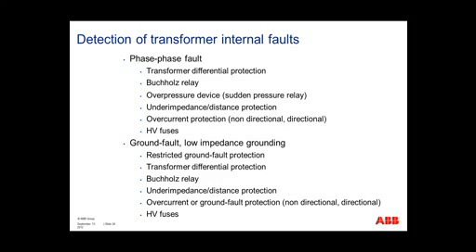How do we detect the internal faults? Well, for faults inside the transformer. For an internal phase-to-phase fault, we have our transformer differential protection, which is going to be our foremost protection. We have a Buchholz relay protection. Our Buchholz relay is a mechanical device that sits inside the transformer. Typically when you have faults inside the transformer, the faults produce heat, and since there's oil surrounding the components, this oil breaks down. When the oil breaks down, bubbles start to form. When these bubbles form, the Buchholz relay can see the flow of bubbles inside the transformer. When the flow of these bubbles gets too much, the Buchholz relay will actually trip, saying that there's an internal fault inside the transformer.